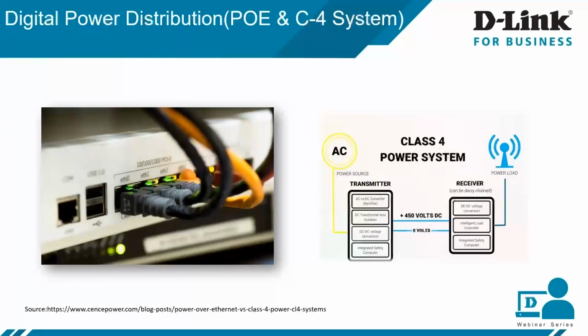Now coming to class 4 application, or class 4 DC power distribution system. We've seen certain limitations in PoE, but it is more prevalent and decade-old technology, safe from fire initiation and protection from electric shock. Similarly, class 4 system can provide safely 450 volt DC, and there is pre-fault detection for any fault occurring. Class 4 systems are considered safe from electric shock and fire initiation standpoint, same as PoE, but they are not power limited, whereas PoE had a power limitation of 100 watt or 90 watt. Instead, they are fault managed.